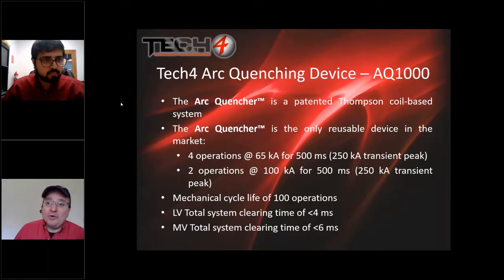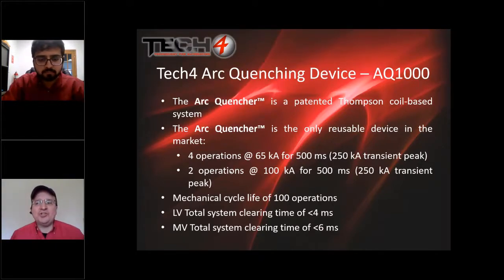So while resettability is important, it should be noted that no arc quencher should ever have to be reset 2 times. After the first arc flash event, it's expected that you would take the appropriate steps to remediate the electrical safe work practices in compliance with NFPA 70E, and/or correct the equipment conditions that allowed such an event to take place. So go ahead, Vivek.